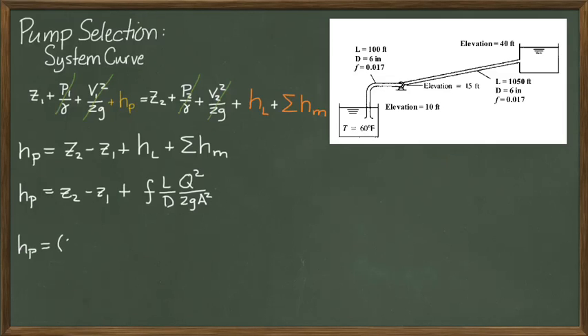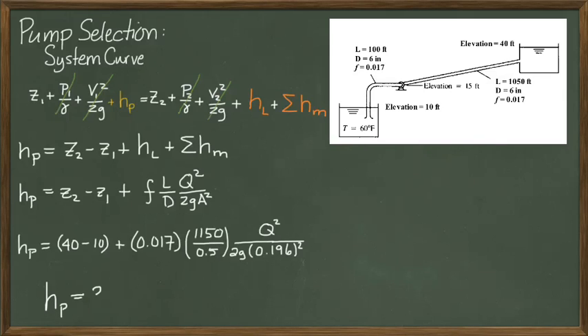So knowing that we're going to use Darcy-Weisbach, we can actually put in the specific values that were given to us in the problem and calculate the pump head in terms of the elevation head plus some factor times the Q, times the flow rate. So that gets us this equation where now we can simplify it down to HP is equal to 30 feet, that's the elevation head we need to overcome, plus the friction head that we need to overcome.